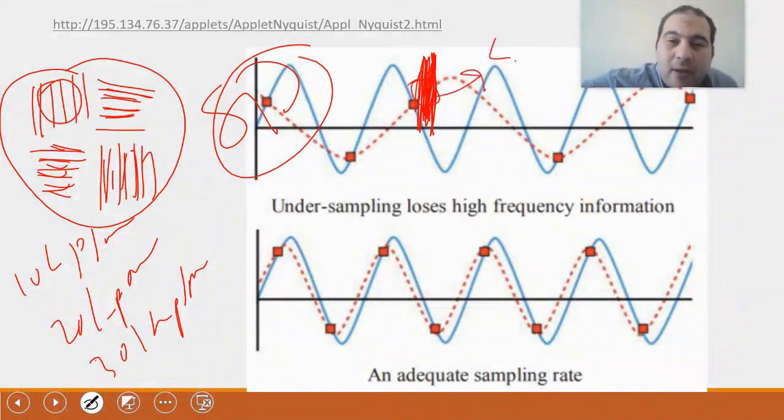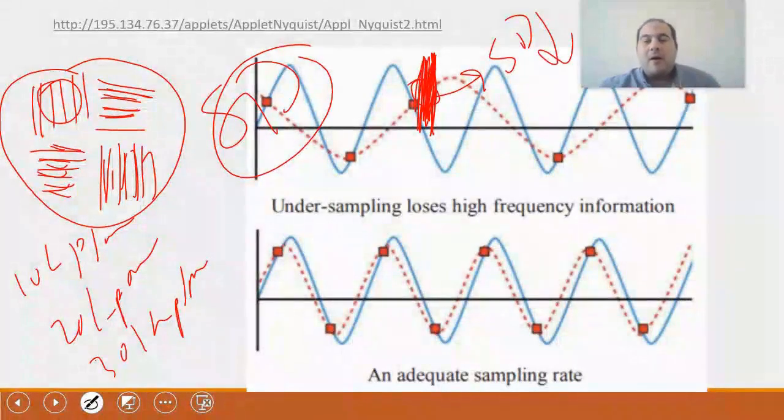For example, if you have something in the body, and you want to slice it, but this thing is next to something else, every time you take your ROI, you find the value of the Hounsfield unit blending into the value next to it. The same idea applies here. All these gaps are not visible, so it sees everything as one. Therefore, the standard deviation here is low, because it reflects the amount of variation present in your image. The value of the standard deviation here represents the extent of the resolution present.